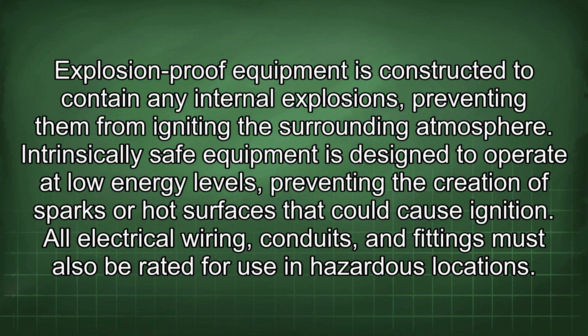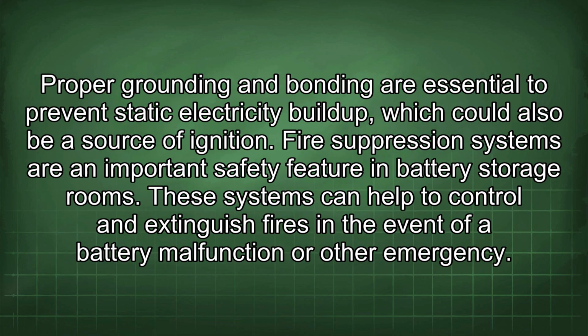All electrical wiring, conduits, and fittings must also be rated for use in hazardous locations. Proper grounding and bonding are essential to prevent static electricity buildup, which could also be a source of ignition. Fire suppression systems are an important safety feature in battery storage rooms. These systems can help to control and extinguish fires in the event of a battery malfunction or other emergency.